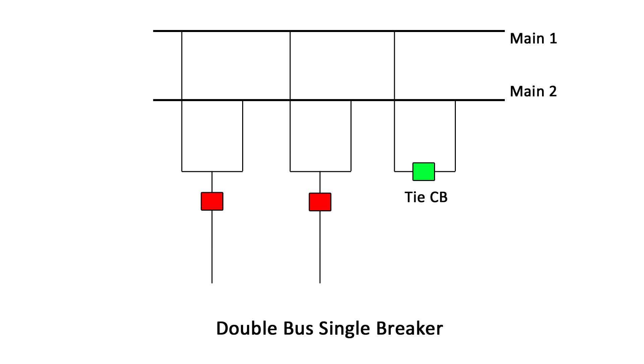A tie breaker connects both main buses and is normally closed, allowing for more flexibility in operation. A fault on one bus requires isolation of the bus, while the circuits are fed from the opposite bus.